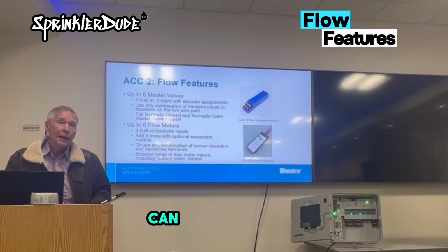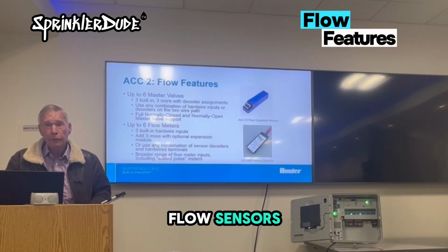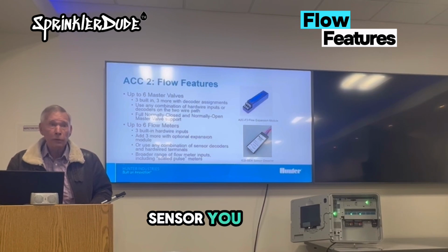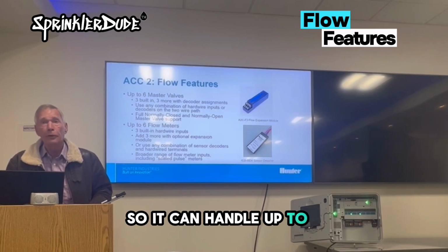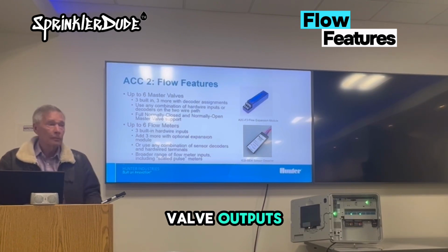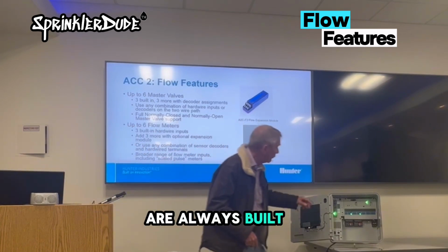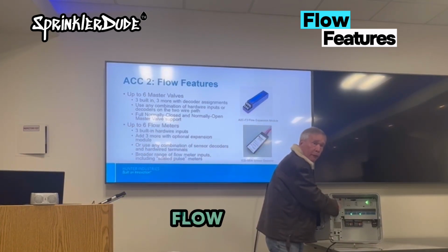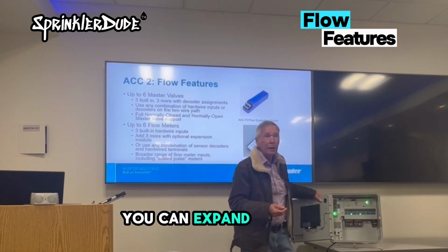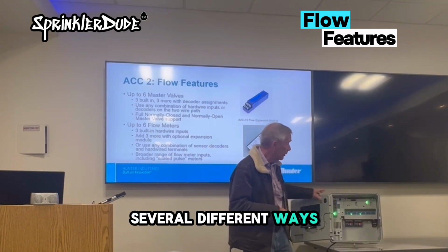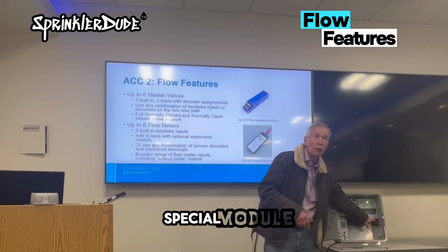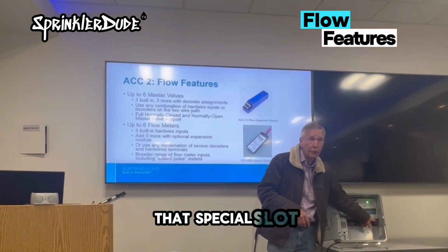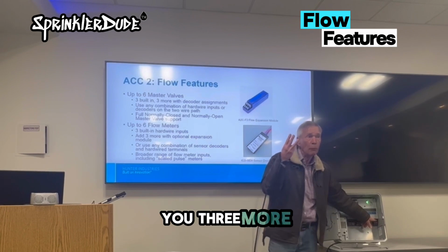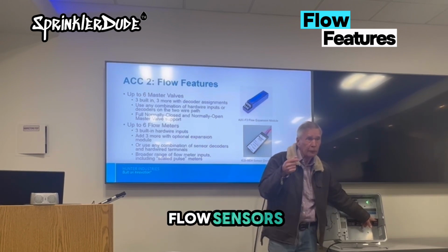This controller can handle up to 6 flow sensors, and wherever you have a flow sensor, you want a master valve, so it can handle up to 6 pump master valve outputs. 3 of them are always built in. There's 3 flow inputs and 3 PMV outputs. You can expand up to 6 several different ways. One of them is this special module that only goes in that special slot, and that gives you 3 more inputs for the flow sensors.